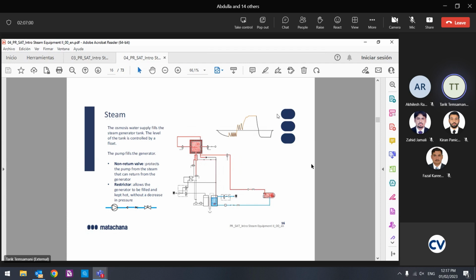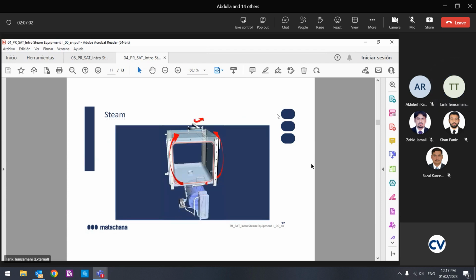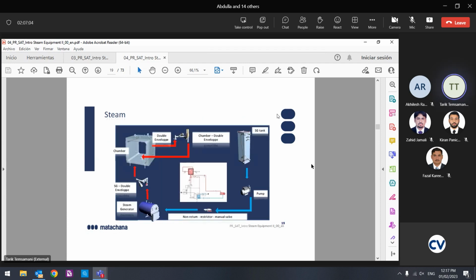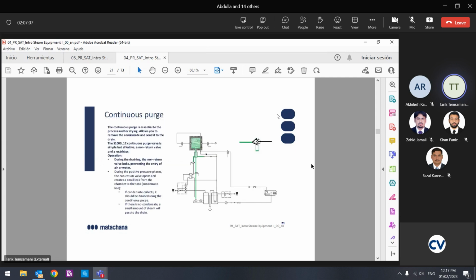Okay, so continue. And this is where I explain the continuous push. That's very important. We have two circuits for continuous push, one for the jacket and the other for the chamber. Okay, two continuous purges, because as I told you, we put steam in the jacket and from the jacket to the chamber.